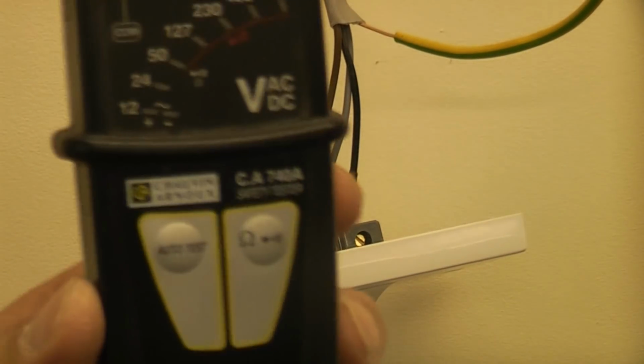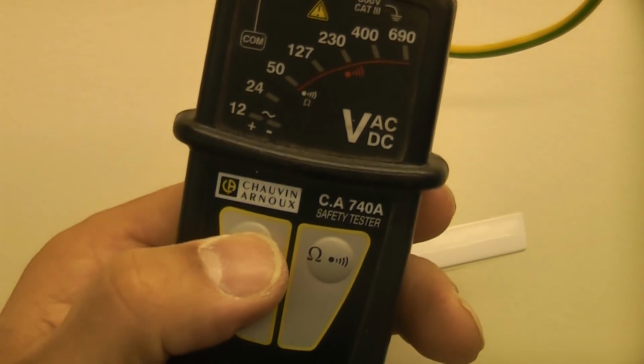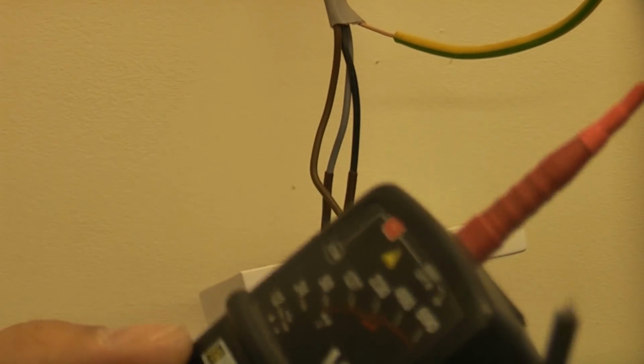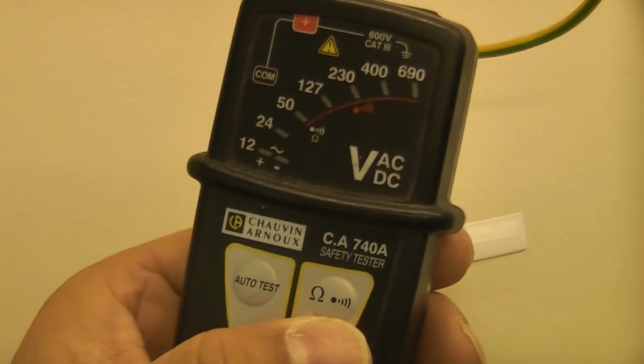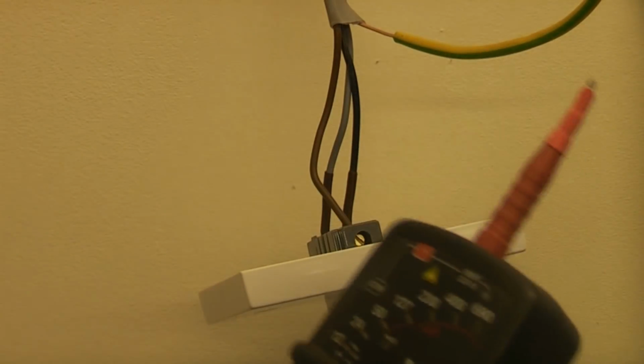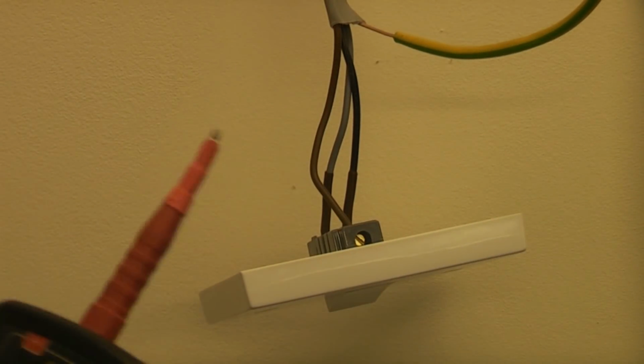So before I use the tester, I'm going to test that it's working okay by pressing the auto test function. I'm then going to test that the leads are in good condition by doing a continuity test. So I'm going to touch the two leads together and then press the button. And you can see that they are working fine. We can now do a test on this to ensure that it is dead.